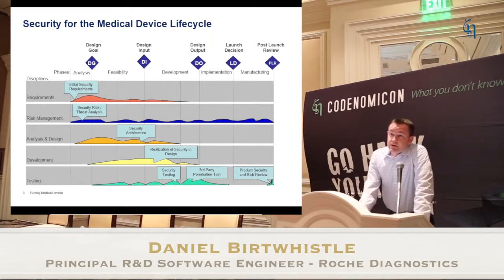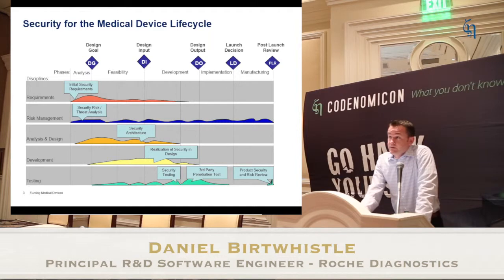Risk management is where it begins, and this alludes to what FDA is also guiding the rest of the manufacturers. It's extremely important that threat modeling be done inside of medical devices, especially ones that communicate. This is where you should realize that your product operates in a context where someone might intentionally misuse that system, and you have to be defensive in your architecture, your design, and your implementation. So, of course, you'll realize this somehow and put the developers on the right tracks, hopefully at your security architecture phase. Then you can review all of their code in your testing.